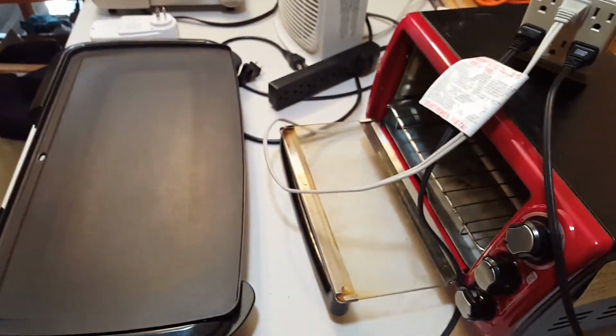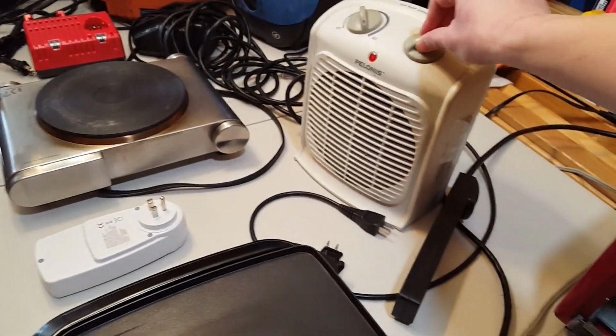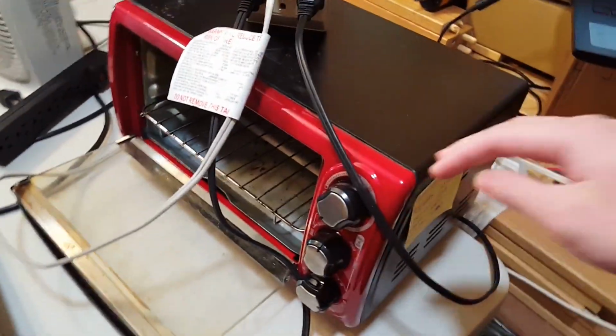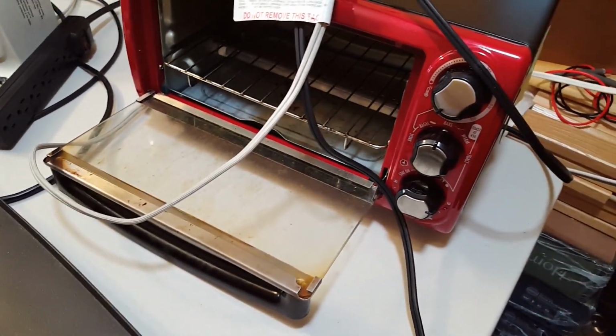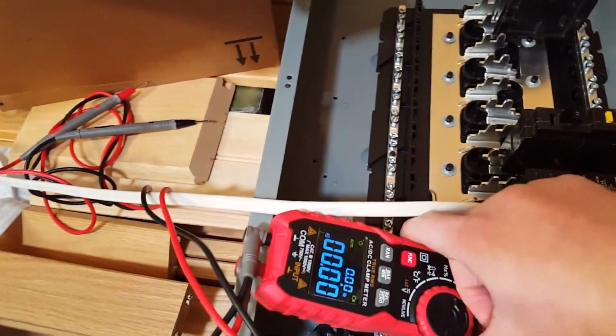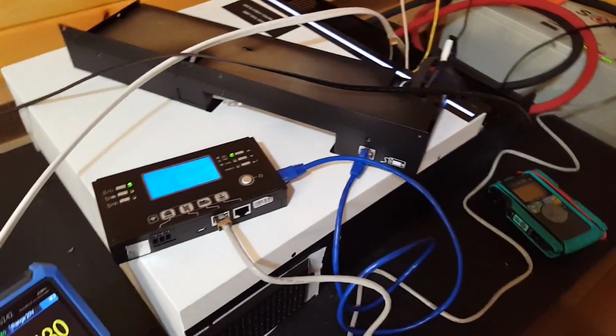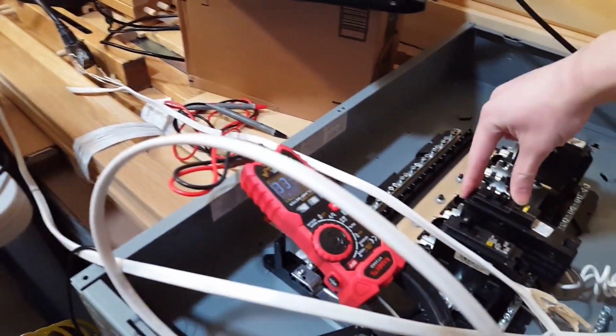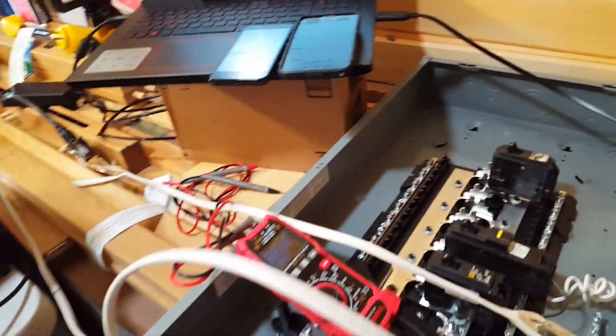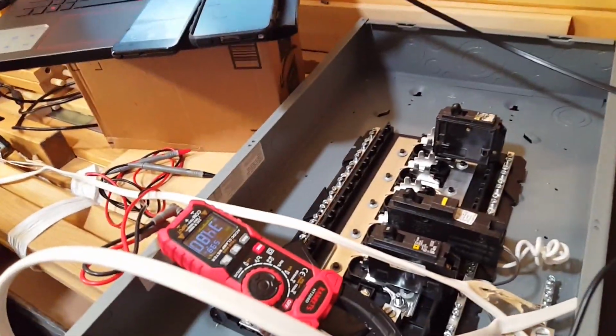Okay. The loads we'll be testing with: a 1500 watt electric pan, the space heater on the high setting, 1500 watts, and this toaster oven on the high setting, which is bake, also at 1000. We'll be looking at AC amps, and we'll also measure DC amps on the battery as well. So let's switch the loads on first. We're still in bypass, and I'll switch off the AC input.